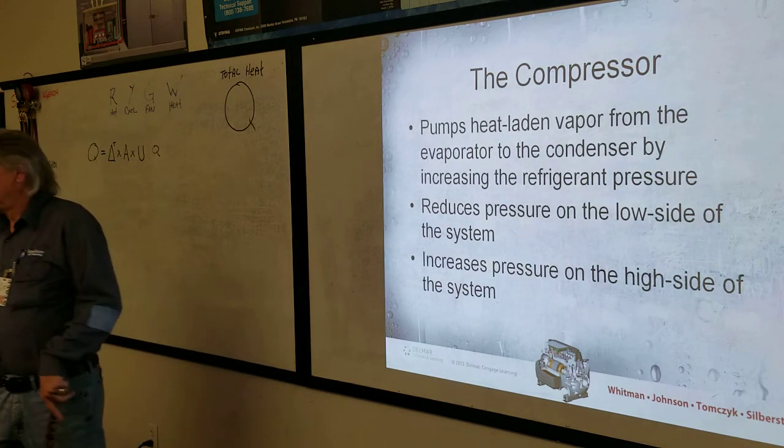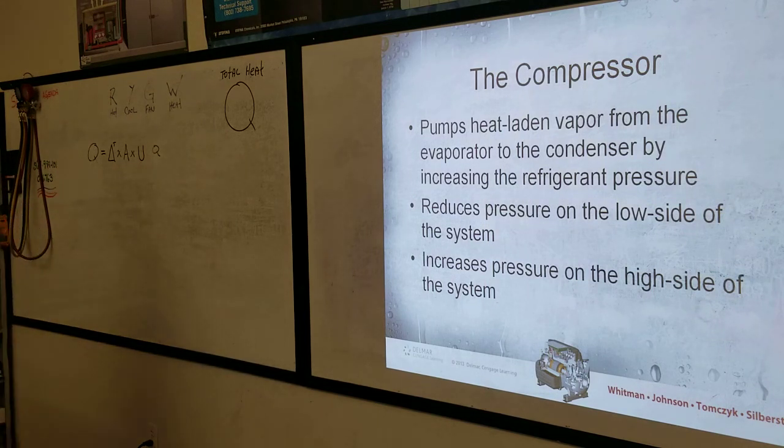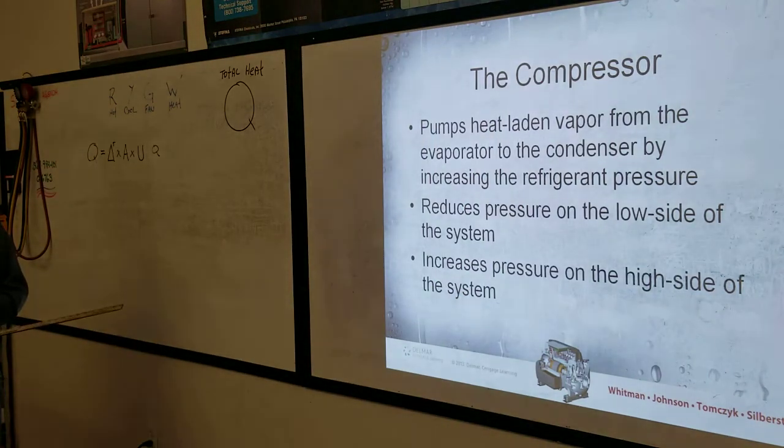Okay. Moving on. The compressor pumps heat-laden vapor from the evaporator to the condenser by increasing the refrigerant pressure. It reduces pressure on the low side of the system and increases pressure on the high side of the system.